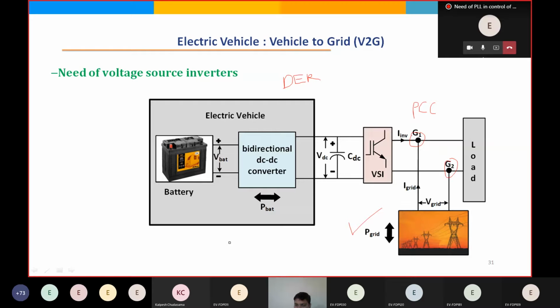But when you connect the inverter to the grid, you have to take care. There are going to be some losses. You are never going to connect the inverter directly; there are going to be some passive filters and some cables. Some losses will take place in the cable impedance and in the passives. Some voltage drop, not losses, but voltage drop is the key issue, will take place in your cable. The inductors in your passive element will have some resistance, right? It's not an ideal inductor, so some voltage drop will take place. You have to take care of all those things.